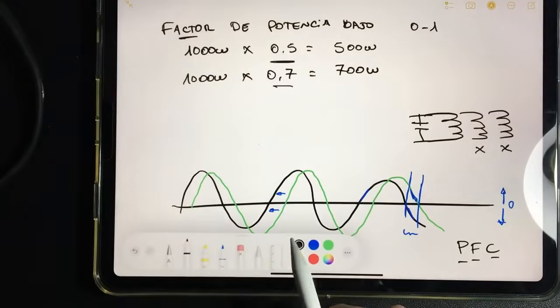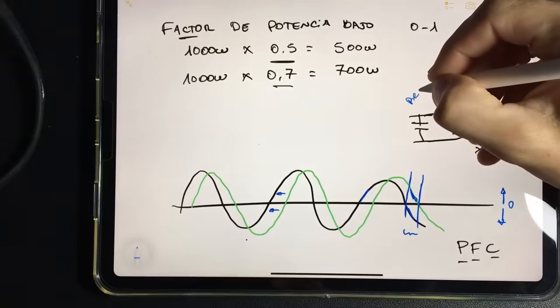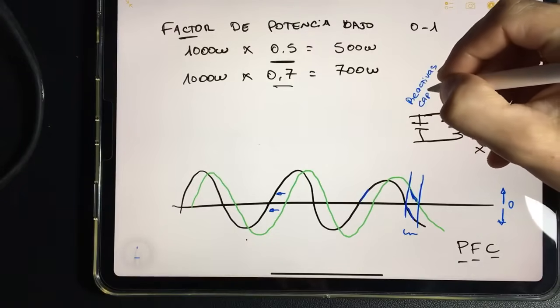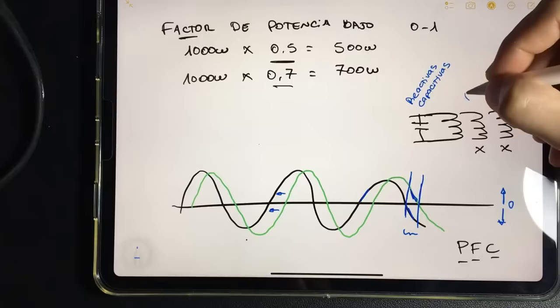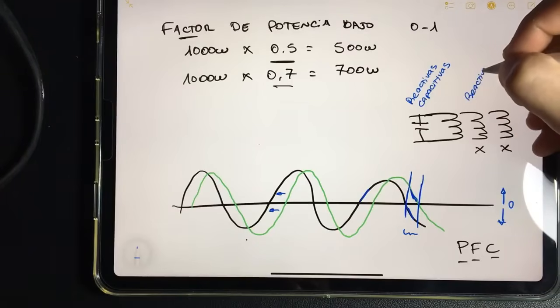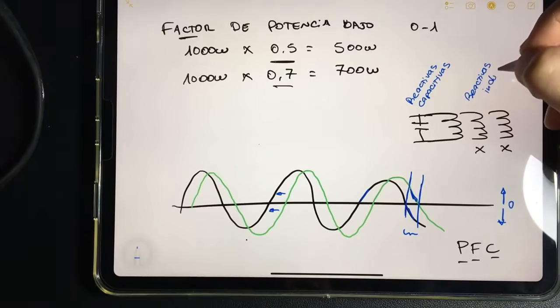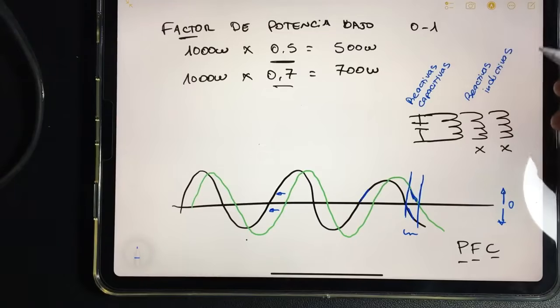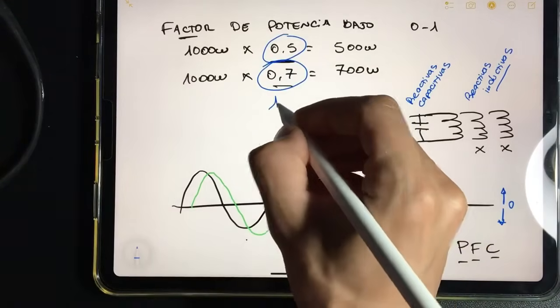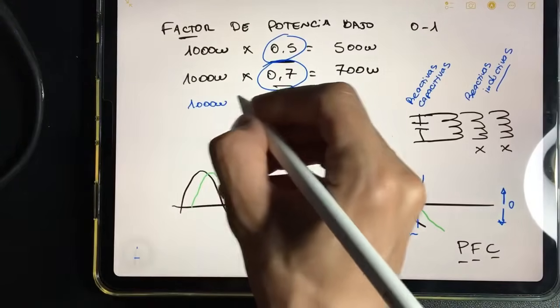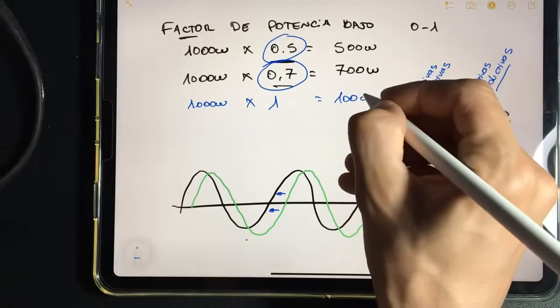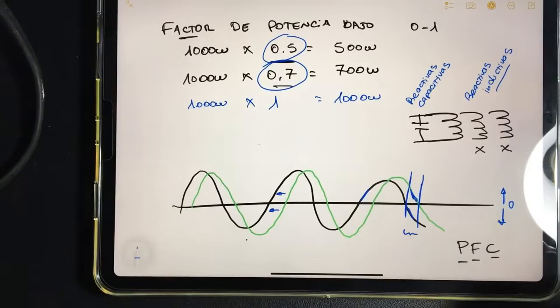The capacitors are capacitive reactive loads, and coils are inductive reactive loads. If I have inductive loads, I have to place capacitive ones, and if I have capacitive ones, I have to place inductive ones, to correct the power factor, which is this number I have to raise. The ideal is that it be 1. If they deliver 1000 watts and the power factor is 1, if I correct it exactly, I am taking advantage of all the watts they deliver me. It's hard to get to 1, but you can.